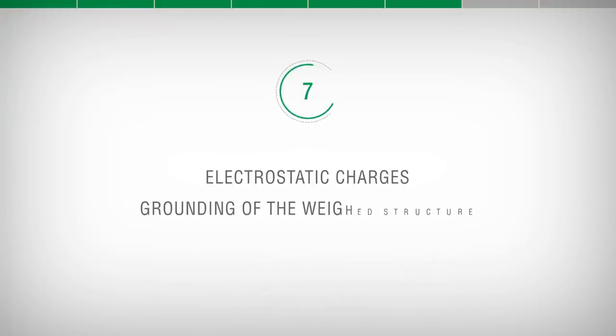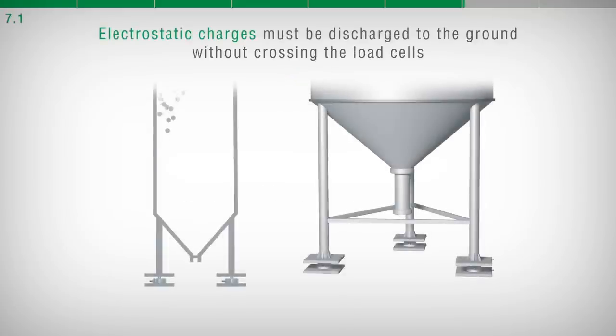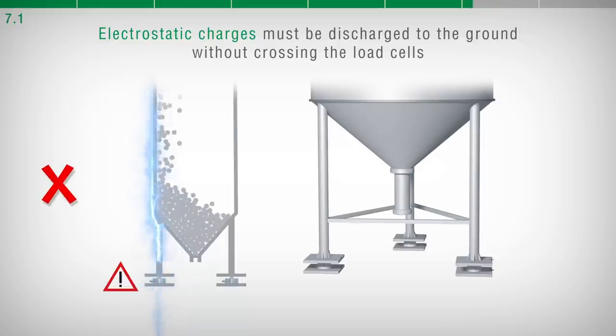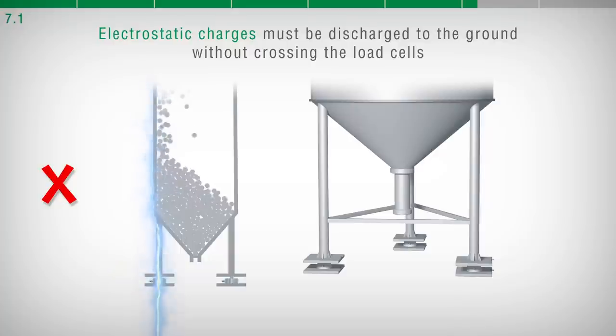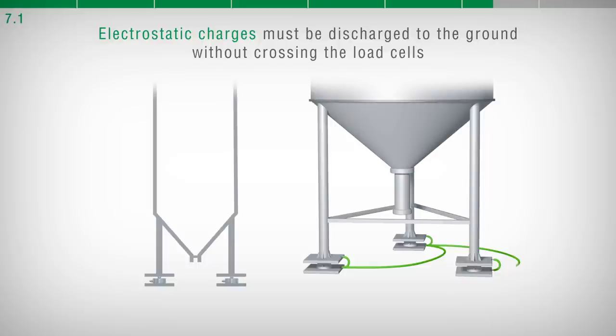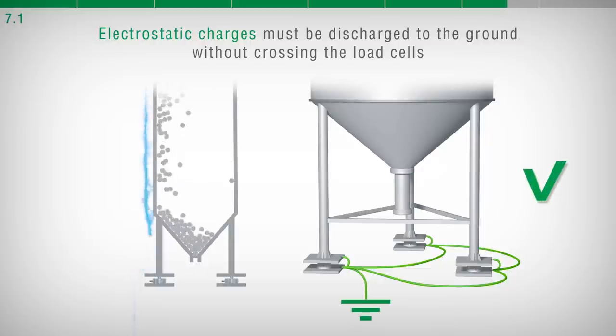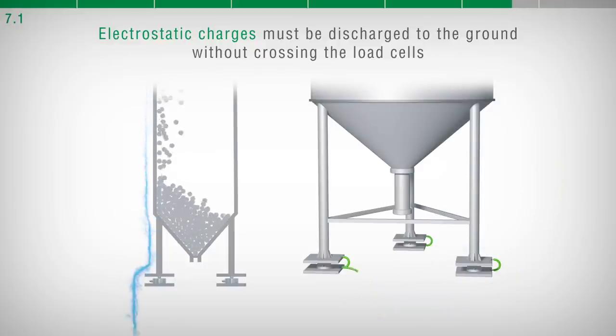Electrostatic charges: Grounding of the weight structure. Electrostatic charges are potentially capable of damaging the load cells. For this reason, it is recommended to connect, by a copper wire of adequate cross-section, the upper support plate of each load cell with the relative lower plate. Then, connect all the lower plates together to the same grounding system. In this way, the electrostatic charges are discharged to the ground without crossing and without damaging the load cells.